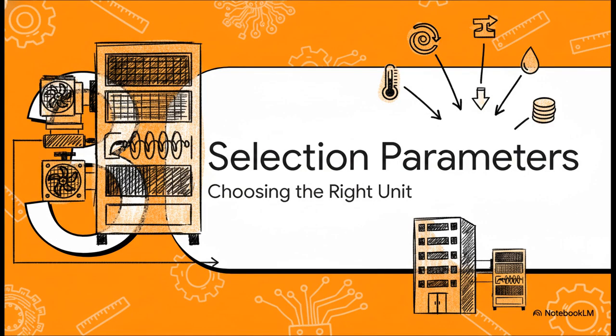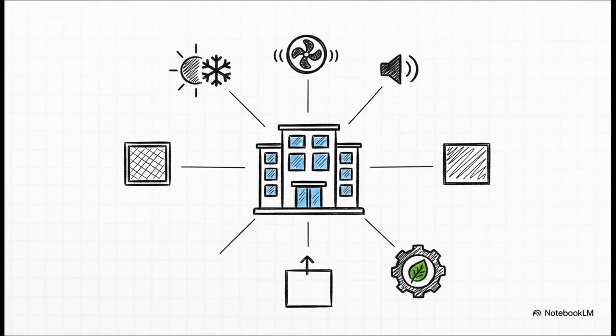Okay, so you get the components, you understand the two main designs. So how does an engineer actually choose the right unit for a specific building? Well, that all comes down to a few key selection parameters. It's really a big balancing act. It all starts with the load calculation. That's figuring out how much heating and cooling in BTUs the building actually needs. That number then dictates the airflow rate you'll need in CFM. From there, you layer on the filtration requirements. You calculate the system's resistance, or what we call static pressure. And then you have to weigh all of that against your targets for energy use and how much noise is acceptable. It's a complex puzzle with a lot of moving pieces.